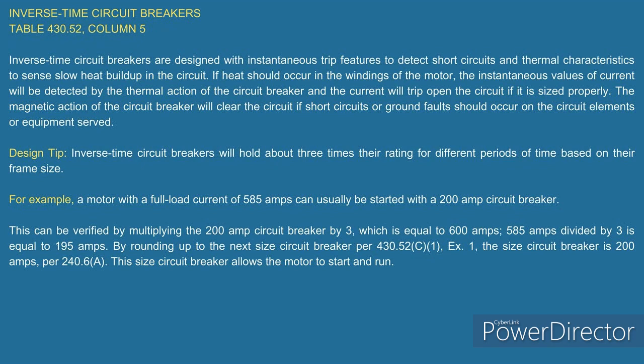Sure. And this is a good example. If I'm looking at an inverse time circuit breaker, how are they designed? They're designed with instantaneous trip features to do what? They detect short circuits, and thermal characteristics to do what? To sense slow heat buildup in the circuit. True. So if heat should occur in the windings of the motor, it will be detected by the thermal action of that circuit breaker. Okay. And based on that and the current, it'll trip open if, of course, it is sized properly. True. So that's why all of this is set up that way.